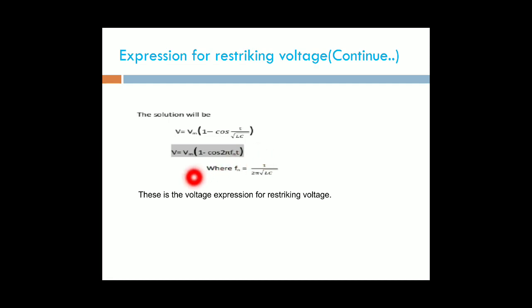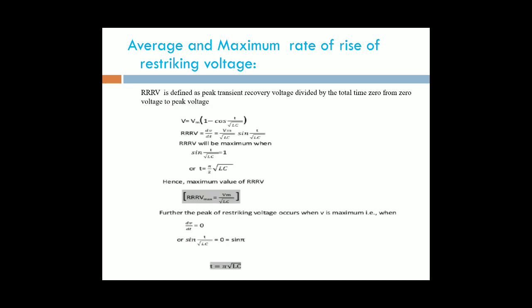Therefore, V equal to Vm into 1 minus cos 2 pi Fn t, where Fn is 1 by 2 pi root LC. This is the natural frequency. This is the voltage expression for the restriking voltage, the voltage obtained across the contacts of the circuit breaker at the starting instant of oscillation: V equal to Vm into 1 minus cos 2 pi Fn t. This is the expression for the restriking voltage.